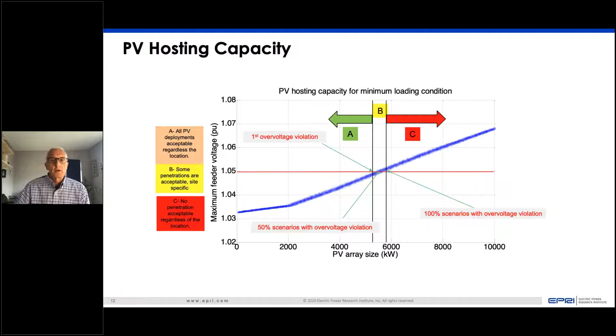That's a concept being applied everywhere, and we can apply that same concept to energy storage or electric vehicle chargers. Electric vehicle chargers are kind of the opposite from a voltage impact point of view. As more cars are charging and load is being drawn through the distribution system, we look at the point where the voltage drop becomes more significant than we can accept, and we would have to do something to support the voltage: reconductoring, new transformers, voltage regulators, to handle more electric vehicle chargers on that circuit. So the concept of hosting capacity will be a very important one going forward, part of our distribution planners' toolkit, looking at these new kinds of loads.